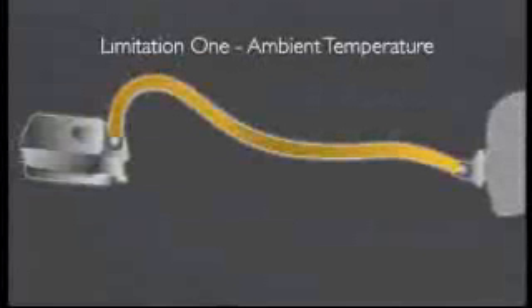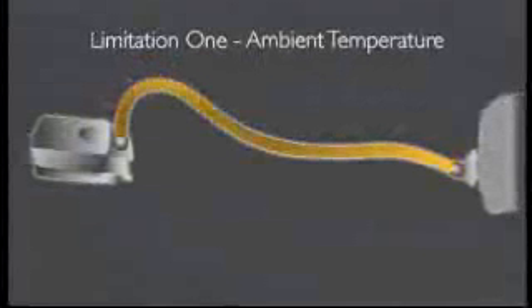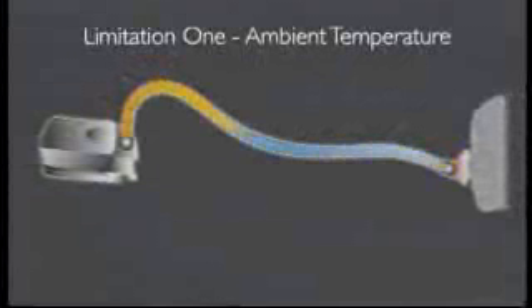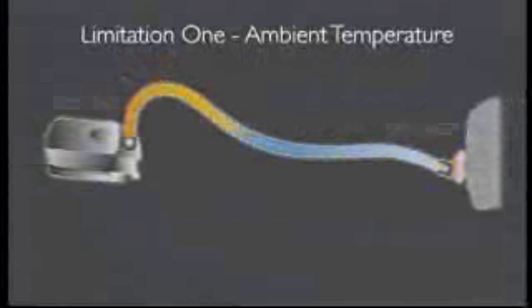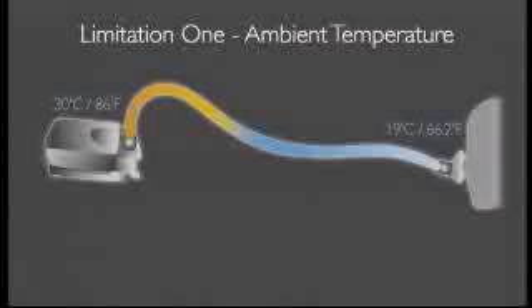Conventional heated humidification systems are unable to achieve these levels due to three major limitations. The first is ambient room temperature. The humidity output of a conventional heated humidification system is restricted by the amount of moisture the air can hold at the ambient room temperature. Attempting to deliver more humidity will only result in condensation, thus failing to deliver optimal therapy.